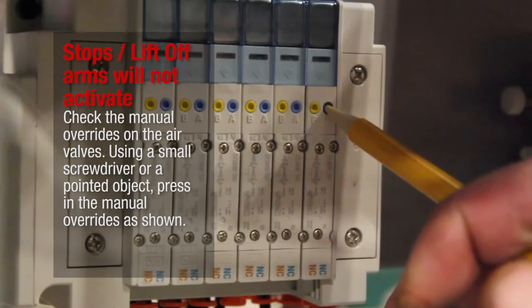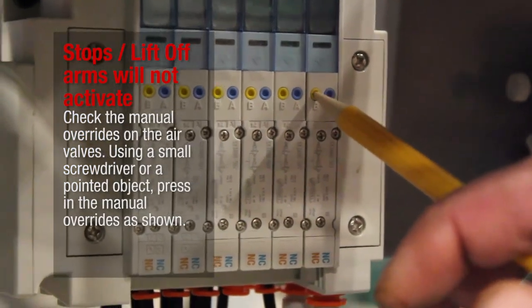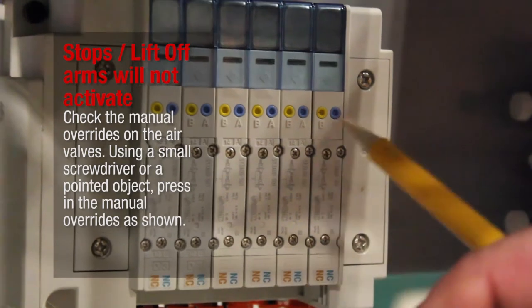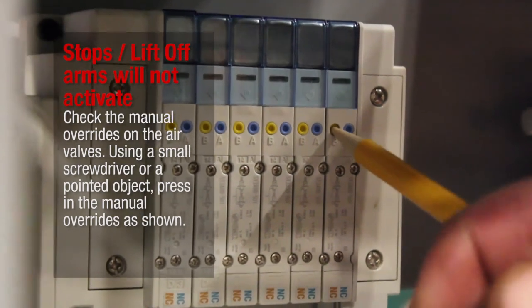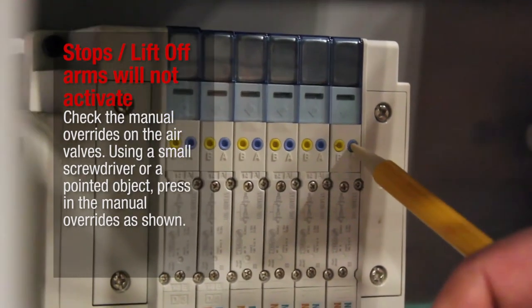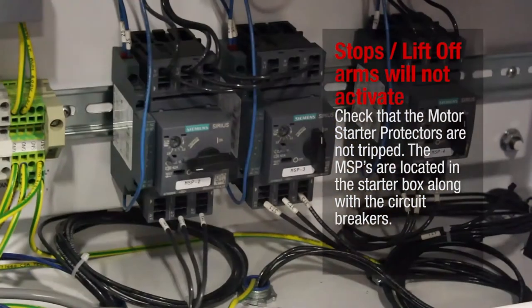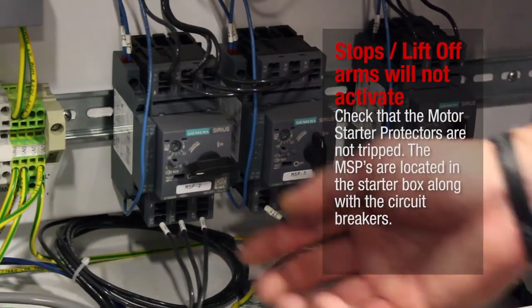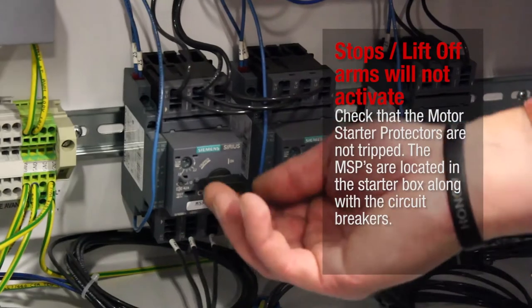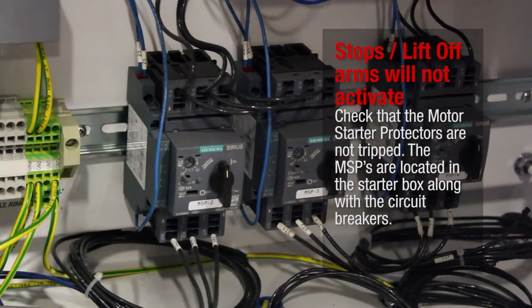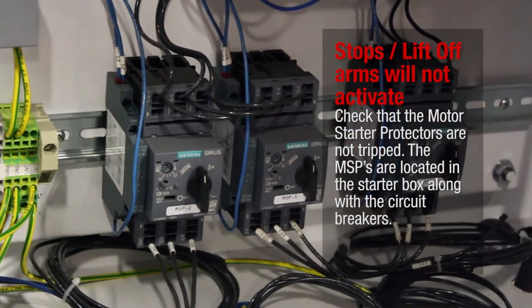Check the manual overrides on the air valves. Using a small screwdriver or a pointed object, press in the manual overrides as shown. Check that the motor starter protectors are not tripped. The MSPs are located in the starter box along with the circuit breakers.